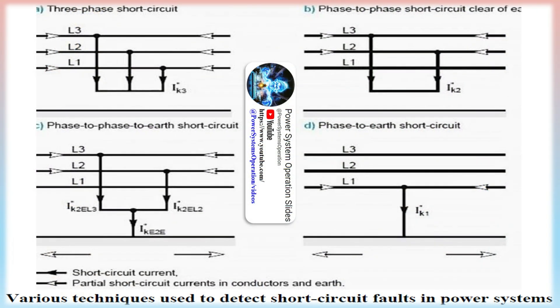Types of short-circuit faults include phase-to-ground faults, where a single-phase conductor makes contact with the ground or an object in contact with the ground. In this type of fault, the voltage between the faulted phase and ground becomes zero, resulting in a sudden increase in current flow. Phase-to-phase faults occur where two or more phase conductors come into contact with each other, resulting in a direct path for current flow between the phases and can cause significant damage to equipment.